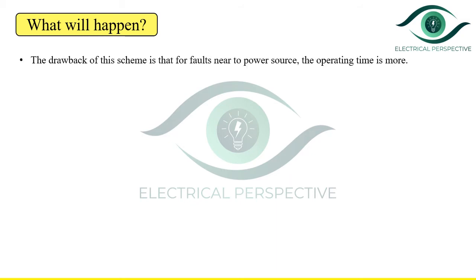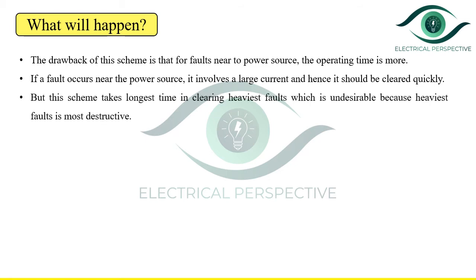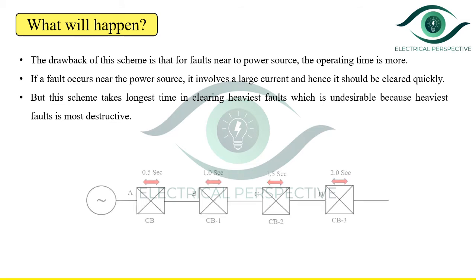An important drawback of this scheme is that for a fault near the power source, the operating time is more. If the fault occurs nearer to the source, it involves a large current and hence should be cleared quickly. But this scheme takes the longest time in clearing the heaviest fault, which is undesirable because the heaviest fault is the most destructive.